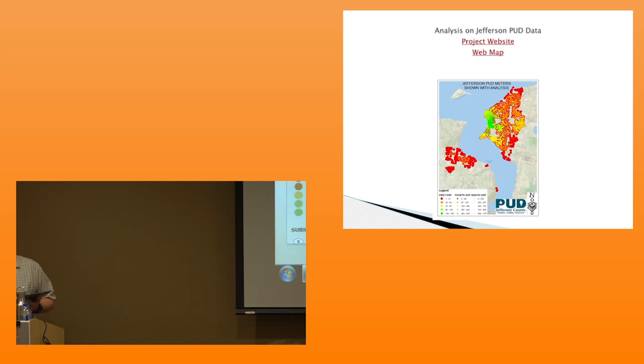So here we symbolize it, of course, green, good, red, bad, red stop, green, go, however you want to say it. And it's very obvious here on this Cape George area that's very dense. Any of those are going to pick up all the neighboring meters. But what I'm really looking for is something outside of the dense area that has a green dot in the middle as a center point. And that to me says that I'm in the highest class. I can see 885 meters around me by the 8th hop, and I'm on the edge of a dense area, and I'm close to another dense area.